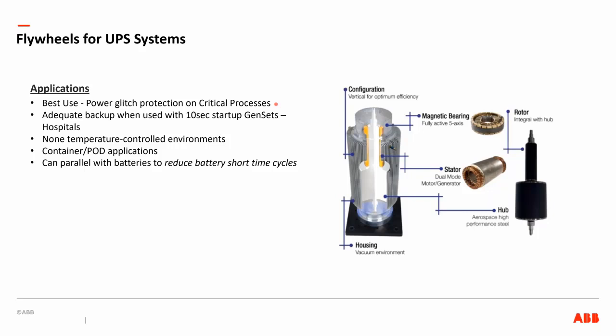One thing to bear in mind here is that with the UPS, make sure this is something that has been tested and approved by the UPS vendor. Not all UPSs understand flywheels. In the flywheel, there's electronics that take whatever power, whether it's AC or DC, coming from the generator driven by the flywheel and convert it to DC power, so it looks like a battery for the UPS. When the UPS is charging, it's accelerating the flywheel, and when it needs power, it's just decelerating the flywheel, and the flywheel is generating DC power.